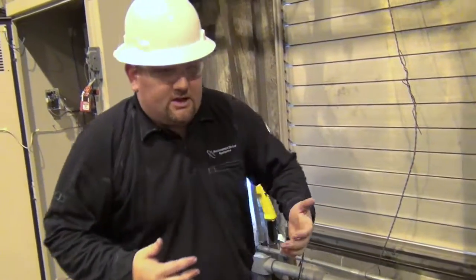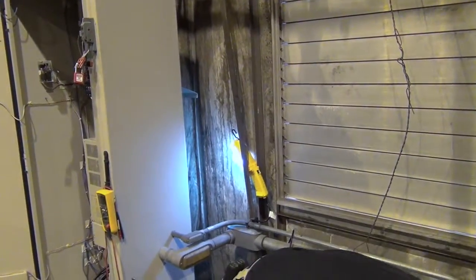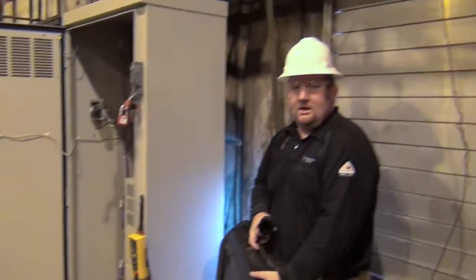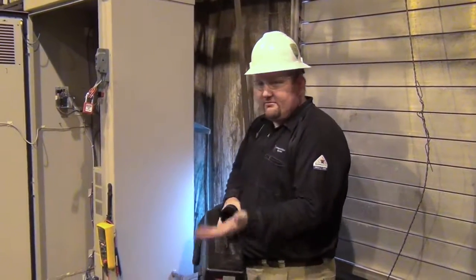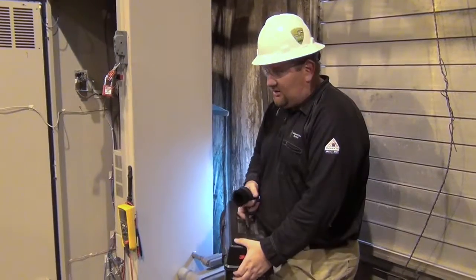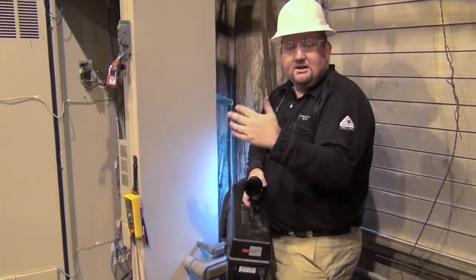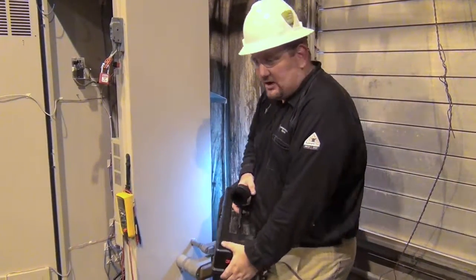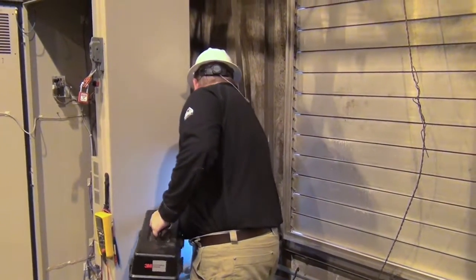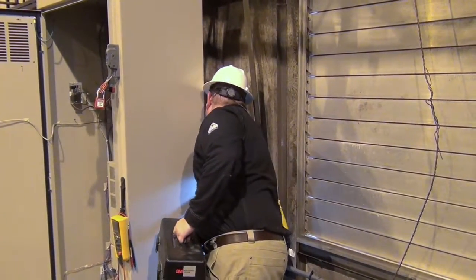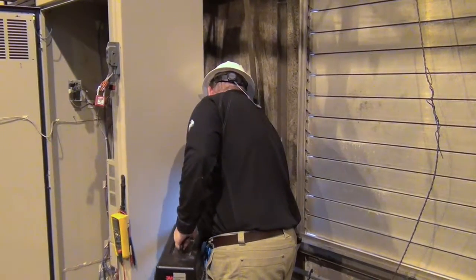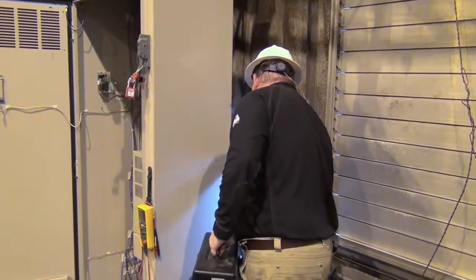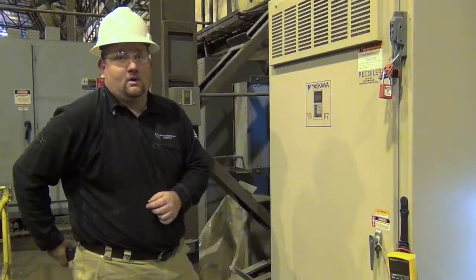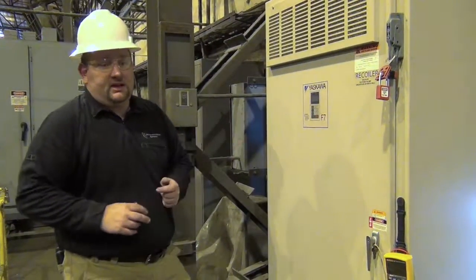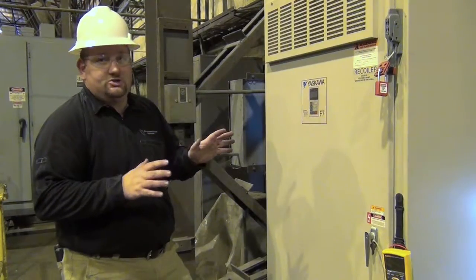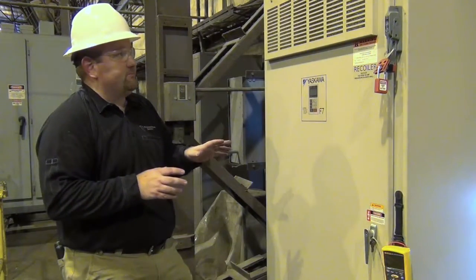Now on the heatsink, I'm going to take a rag and wipe down everything that I possibly can. As a final step for the heatsink, after I've blown the air up through the back, I'm going to take the vacuum and just run it along the very top of the heatsink to pick up any of the dust that has settled back down on the drive. So now that we've gotten the heatsink cleaned up as best as we possibly can, you'll notice there's a huge difference in the before and after with just a very simple maintenance.